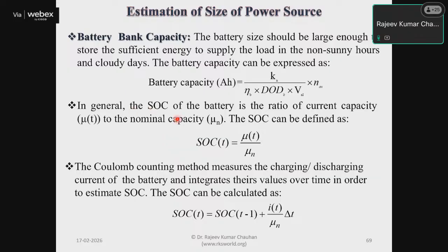Another parameter needed for the backup period is the state of charge of the battery. It is the ratio of current capacity to nominal capacity—state of charge with respect to time divided by total capacity. This tells us what percentage of SOC corresponds to how much ampere-hour is left inside the battery. To calculate the state of charge at a particular time instant, there are different methods.